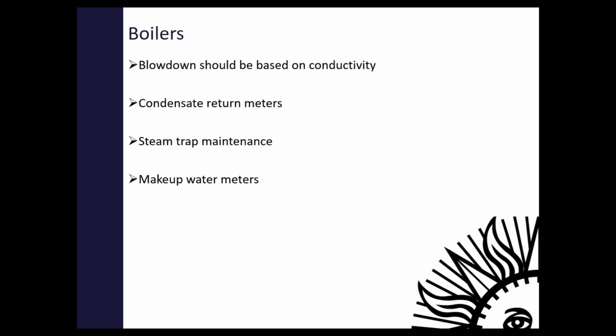Boilers, kind of the same thing. Blowdown should be based on conductivity. Make sure there's no continuous blowdown. Condensate return meters, actually that's another good one with the cooling tower. You should always meter your cooling tower makeup water and blowdown. That is the most accurate way to really determine your cycles of concentration. You can't improve what you don't measure. If you're actually measuring what your blowdown is and what your makeup water coming into your tower is, you can calculate your cycles of concentration more effectively than when you're just measuring conductivity.